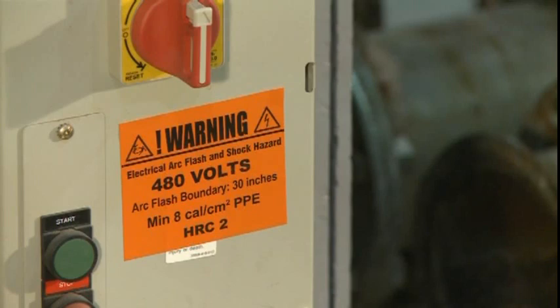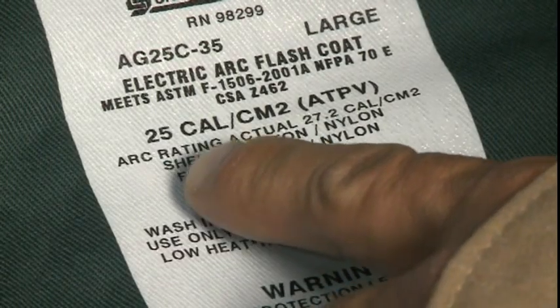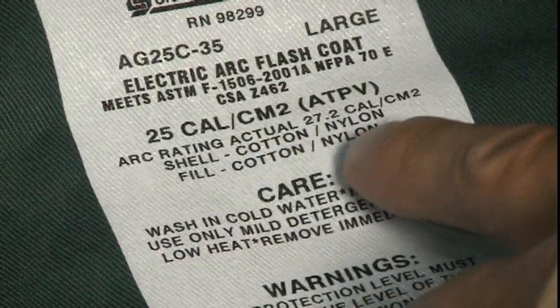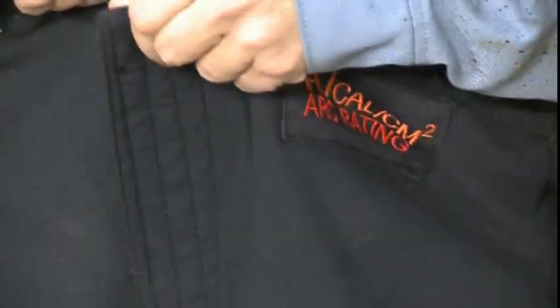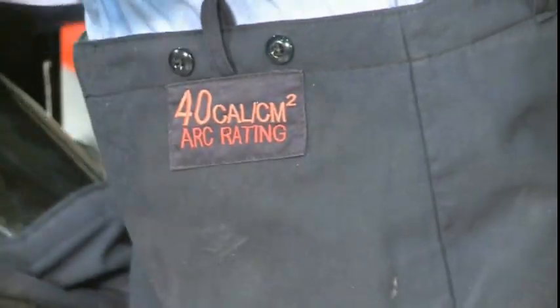And remember that the incident energy level of an arc flash is measured in calories per centimeter squared. The effectiveness of arc-rated clothing and equipment is also measured in calories per centimeter squared. To provide an appropriate level of protection, arc-rated clothing and protective equipment is selected to meet or exceed the incident energy level of a potential arc flash.